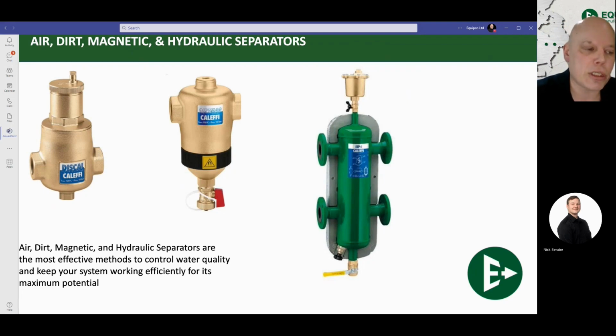In order to be a high efficiency air separator, it has to have media on the inside and not just a steel plate with a baffle, media on the inside to create turbulence in that water, where the air bubbles that you create when you create turbulence can rise to the top. If you're at home and maybe you've got one of these partially drunk water bottles, you shake it, you see all those air bubbles start to be created in the water. That's because we are creating turbulence. High efficiency air separators create that turbulence, and they have media inside to coalesce those little air bubbles and bring that to the top and burp it out of the system. Only media meets the 214. A plate does not. I want to be clear on that one, because there are some products out there that claim to have all the bells and whistles, but they do not meet minimum code. So just something to keep in mind.